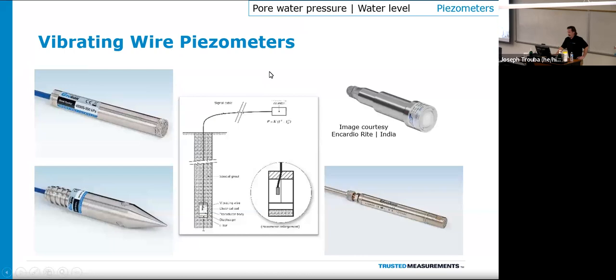So they also come in corrosion resistant types. So you can manufacture these, and other companies can manufacture these, with titanium or Inconel, which is a nickel chromium alloy, often used in very corrosive environments. It handles a low or very high pH as well. In addition to that, I want to take cable types into consideration. So these come with a variety of different signal cables: PVC, polyurethane, stainless steel. We have heavy duty armored cables for high shearing environments and near blasting. So there's a lot of different things that go into picking these instruments, and a lot of different options that exist out there.